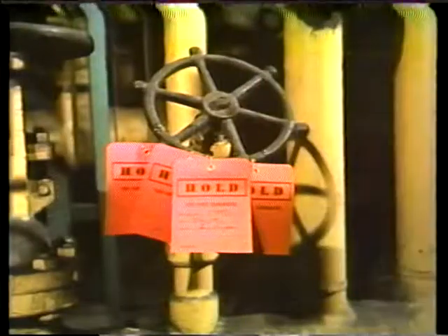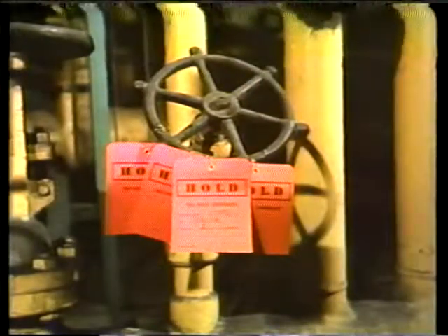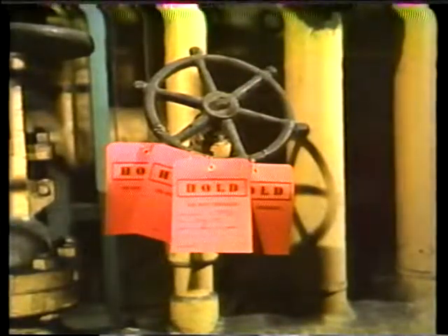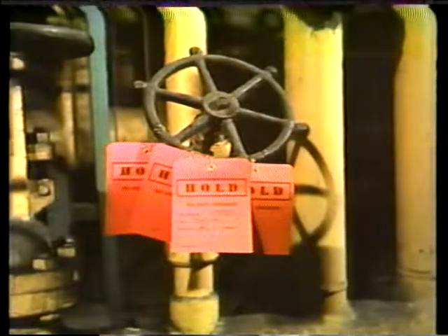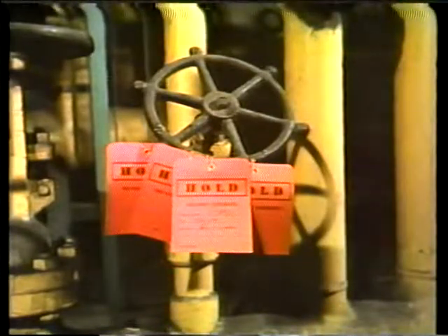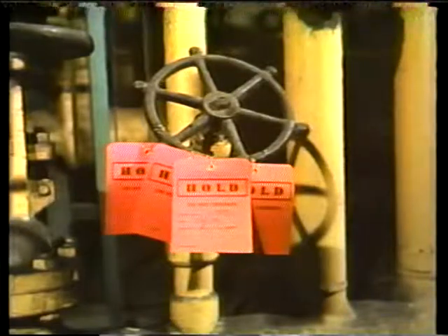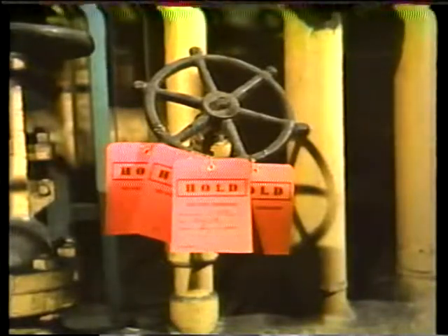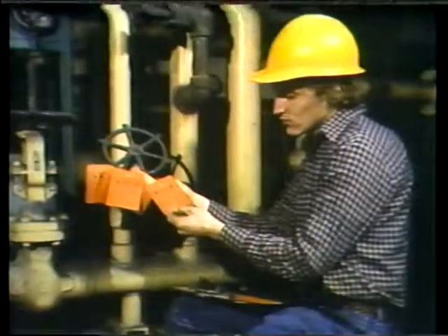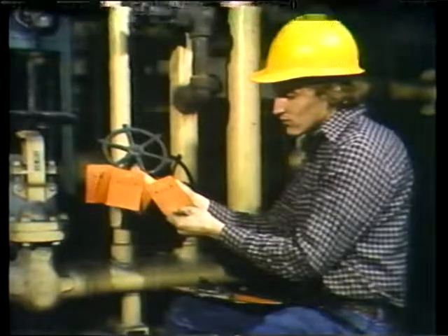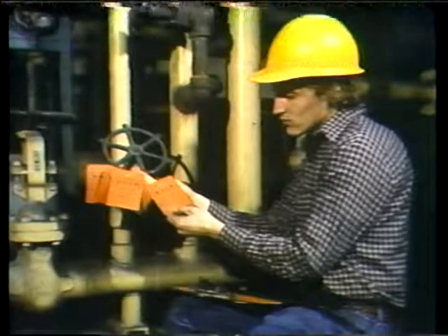Now, you may run into a situation in which several maintenance groups are working on jobs involving the same equipment. Then a breaker or valve for that equipment may have more than one red tag attached to it. Now, if a component appears on your tag list, make sure you put a tag on it, regardless of how many other tags may be hanging from it. There must be a tag for every job, and you continue your tagging until the checklist is finished.